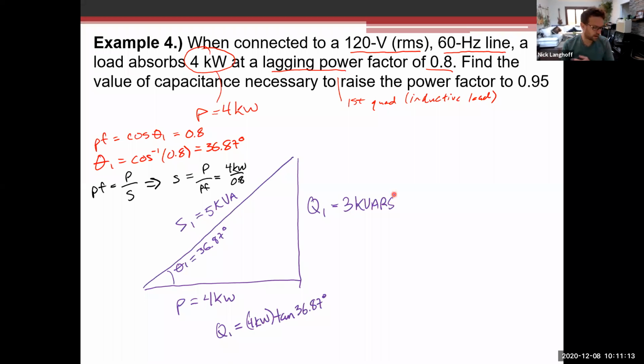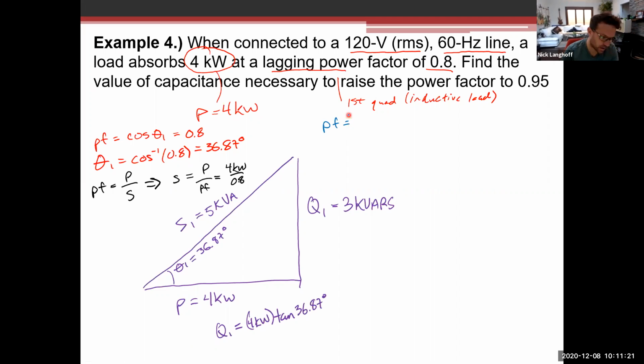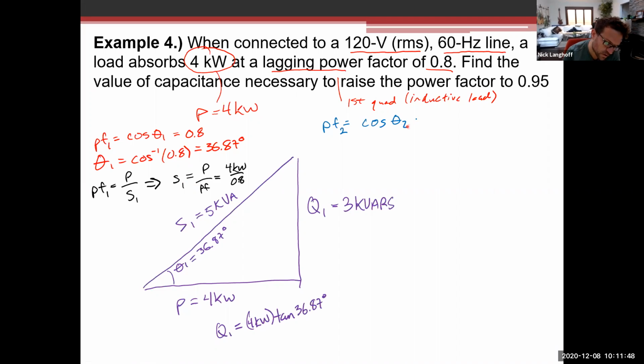Now let's take a look at where we want to get to. We know the power factor 2 is what we want here—let's call the first one power factor 1, with S1. Power factor 2 should equal the cosine of theta 2, and we've been told we want to increase the power factor to 95%. Taking the inverse cosine of 0.95 gives theta 2 equal to 18.19 degrees.